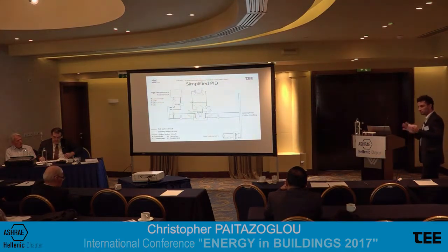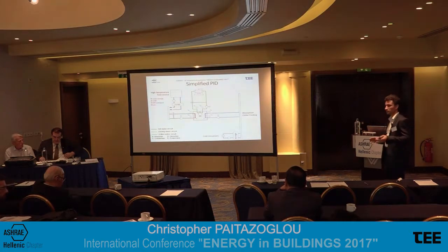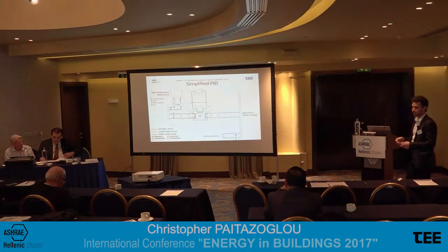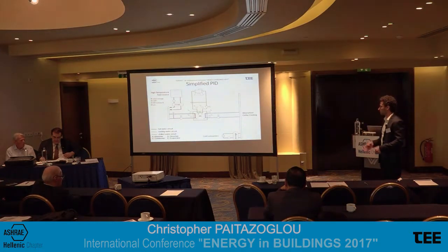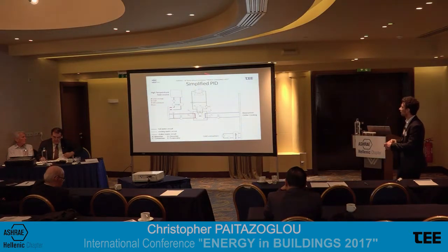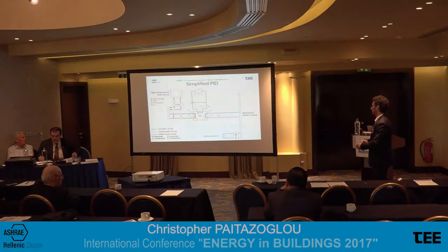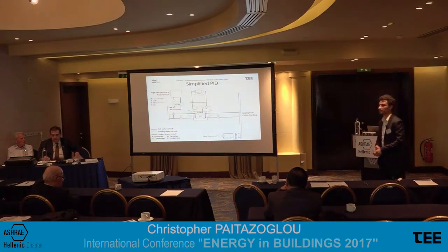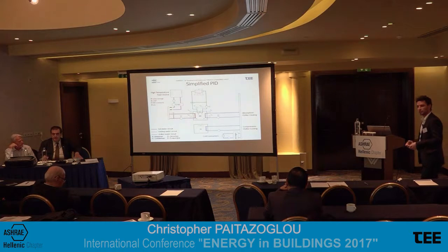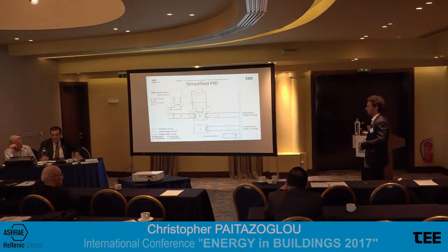So let's get over to a brief simplified PID, process and instrumentation diagram. We have a lot of field tests, a lot of complex systems. I've tried to break them down to a very easy one so that you can understand the results in the end of what we're talking about. So again, we have the absorption chiller that is providing cooling, and we need a high temperature heat source that can be a solar energy and so on in order to drive it. In this case, we're talking about absorption chiller cooling. When the absorption chiller is not enough, or there's a backup system needed, or there's another compression chiller needed, we're talking about compression chiller cooling, that is also feeding the network here.